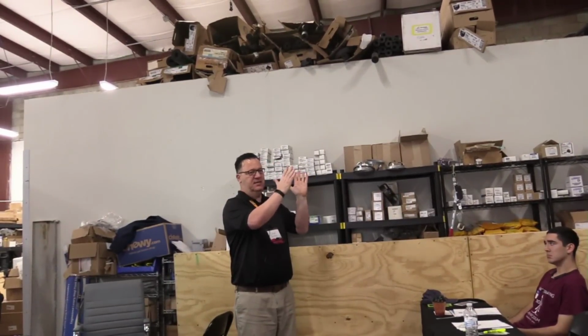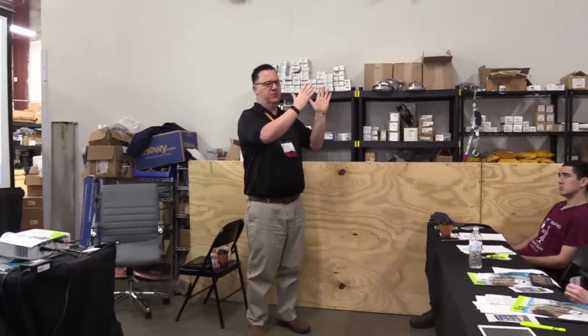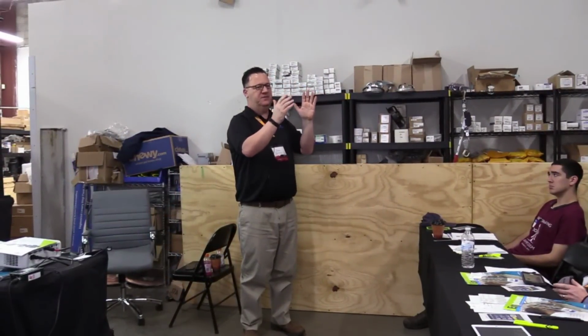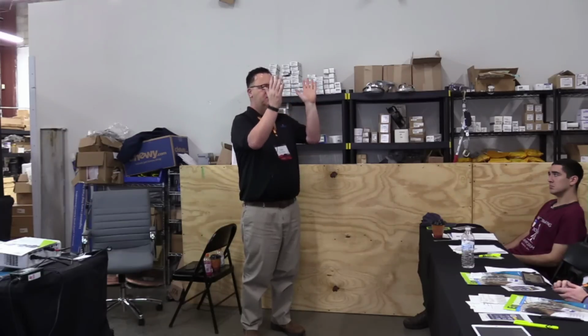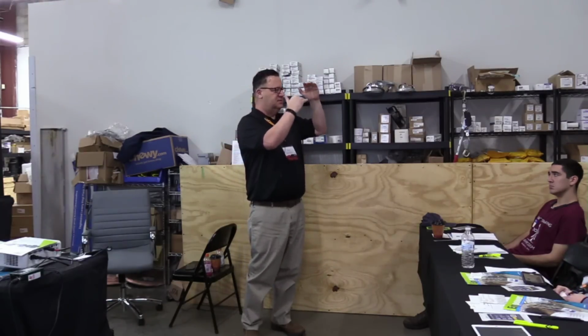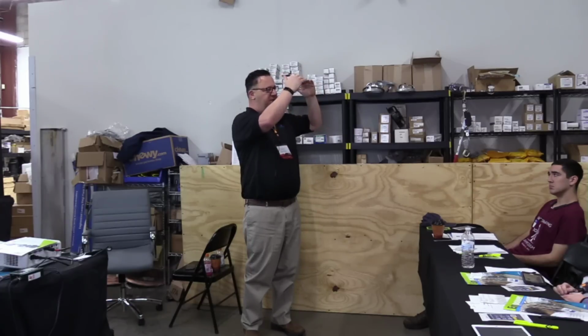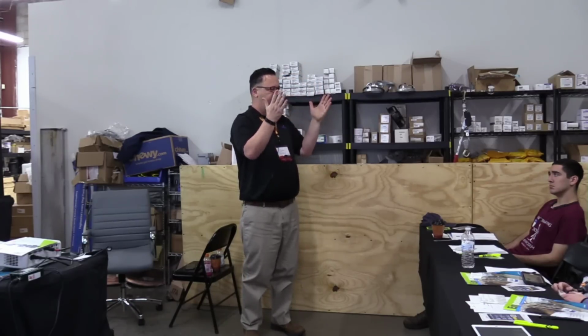So you've got PSIG on your gauges, adding atmospheric pressure, which is 14.7, or standard atmospheric pressure. We rounded up to 15 for easy math. Okay, that changes it to absolute. We take the absolute suction and divide it into the absolute head pressure, and that is whatever that number is when you do the math. If it's 10, then it's 10 to 1. If it's 5, it's 5 to 1. Normally air conditioning is 3 to 1. Medium is around 5 to 1. Those are just rough numbers, and low temperature would be somewhere around 10 to 1.